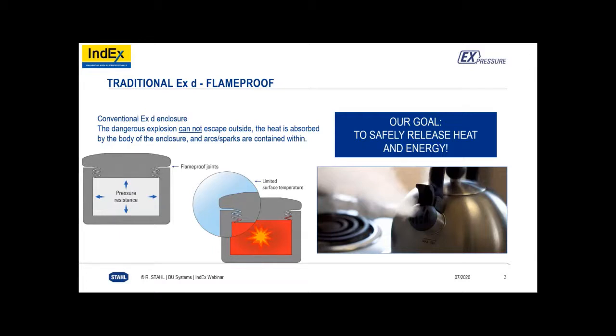In the past, we asked ourselves the following: what if we didn't have to keep the explosion pressure inside the enclosure, but simply release it? What if we could release it to the surrounding environment and at the same time guarantee the same high level of safety? And what if the temperature created during the explosion met the safety criteria in hazardous areas? Our answer and solution to all these questions is the first explosion-proof enclosure which safely releases heat and energy. And this is what ExPressure does from R.Stahl. And this opens.